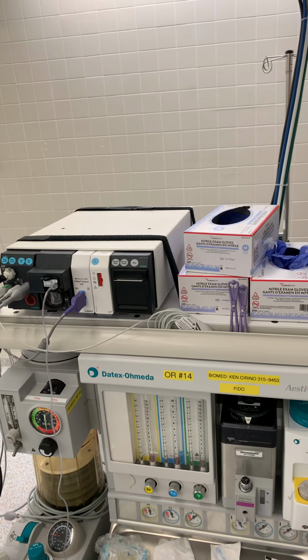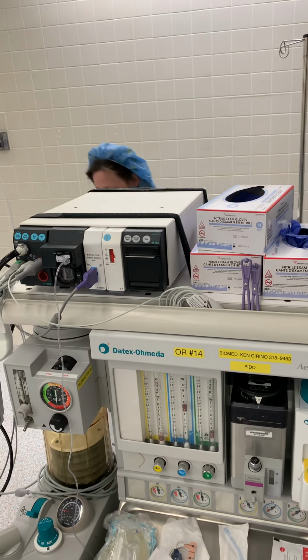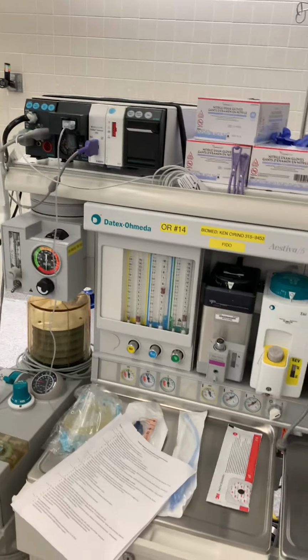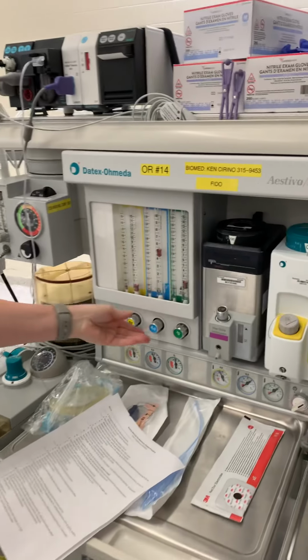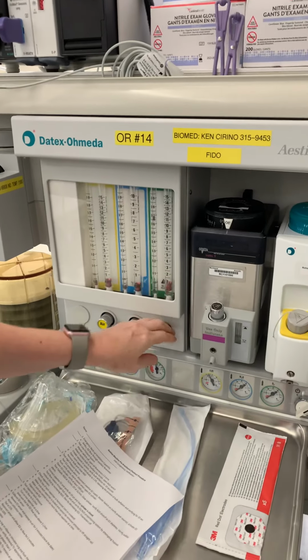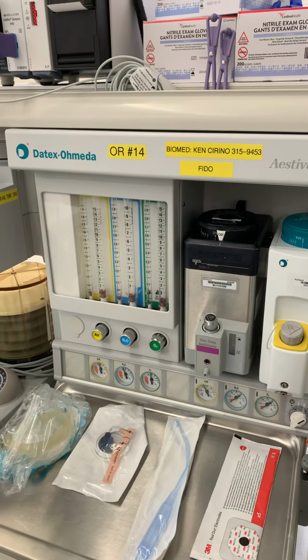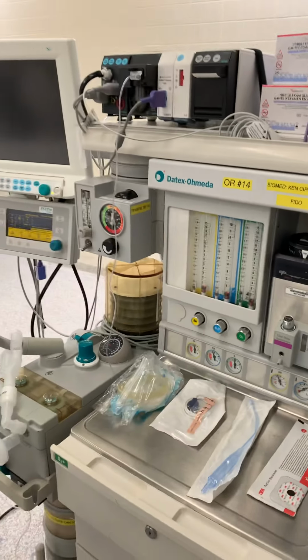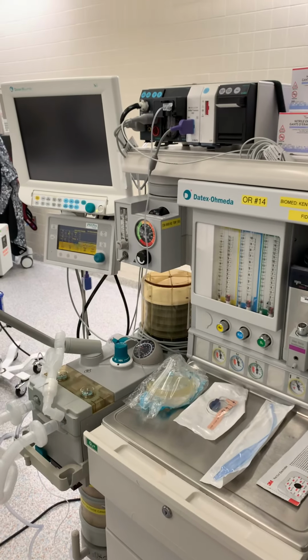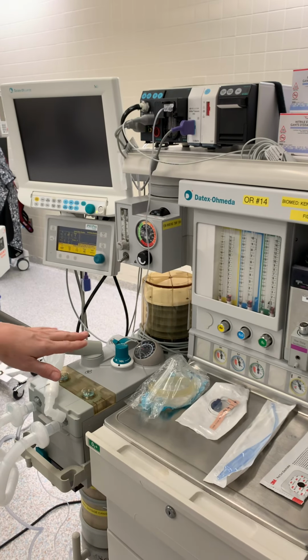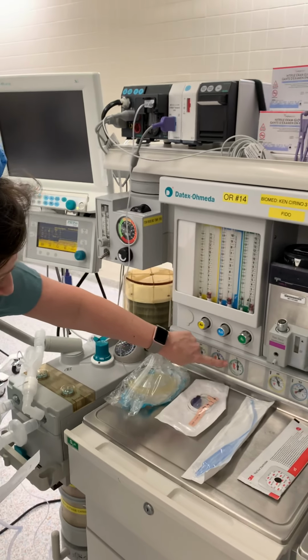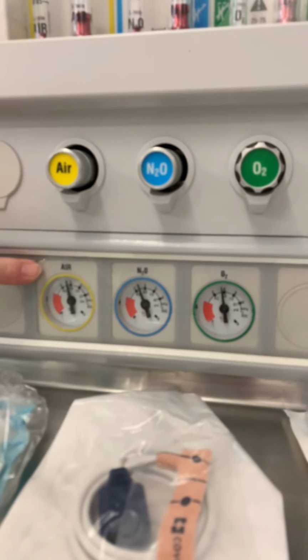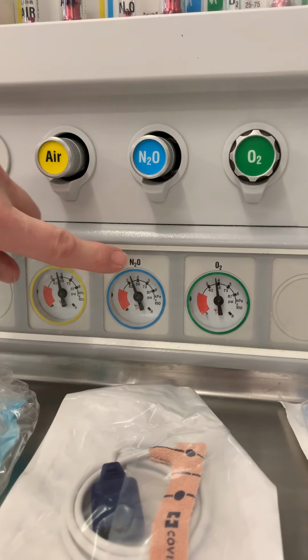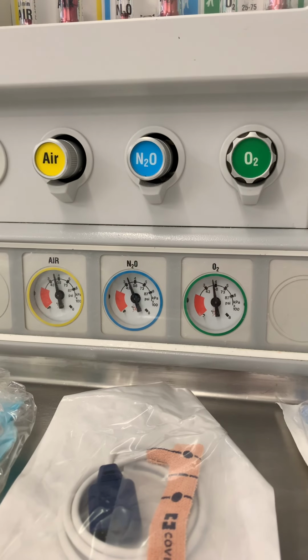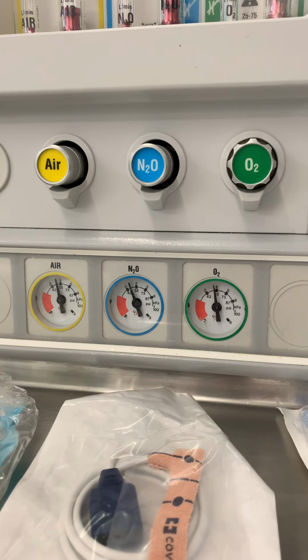Sometimes it takes a little elbow grease to get that reconnected. And now that we have oxygen coming back, we should not hear that alarm anymore. With everything running again, with all the pipelines connected, we should look and make sure that all of our pressures coming from the pipelines are between 45 and 55, and they are. And so we verified that.